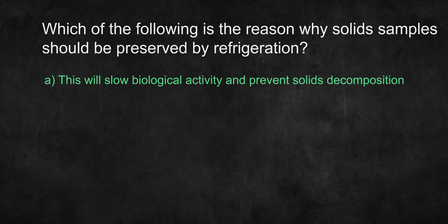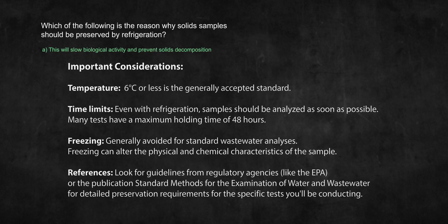The answer is A: this will slow biological activity and prevent solids decomposition. Refrigeration of wastewater samples to a temperature of 6 degrees Celsius or less is crucial because it minimizes biological activity within the sample, slowing down the natural decomposition of solids by microorganisms. Preserving sample integrity ensures that analytical results such as TSS, BOD, and COD accurately represent the wastewater conditions at the time of sampling. It's important to preserve every sample appropriately to receive a valid result. Always refer to a standard operating procedure at your plant or reference guidelines from proper publications such as the EPA or standard methods if you're not sure.